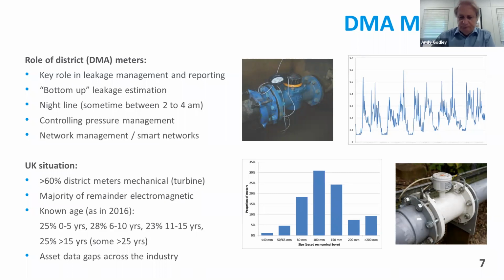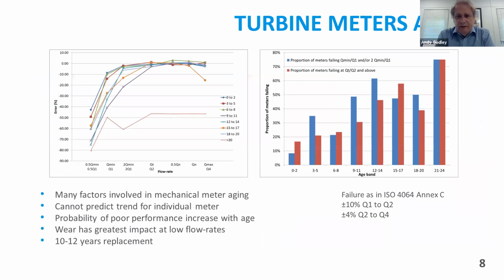So I mentioned that a lot of our stock was quite old, and why is that important? Well, particularly for the turbine meters, we know they tend to age. We know that they are mechanical devices, and wear happens within the bearings, within the components of the meter. That means their performance changes over time. And you can see in that top left graph some examples of meter curves.